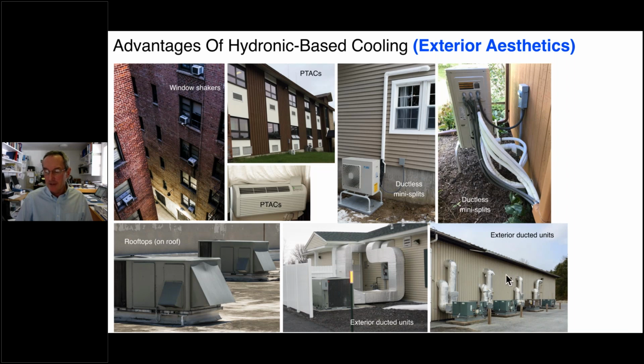This is one of the dollar type stores. Again, upstate New York. We've got ducting with insulation on it. One of the other things I look at here is this metal roof. This is in a location where they easily get 100+ inches of snow in a winter, and sometimes that's going to slide off of that roof. And when it does, it's probably going to land right about on top of those units or on top of that ducting. So from an aesthetic standpoint, these don't excite me too much.